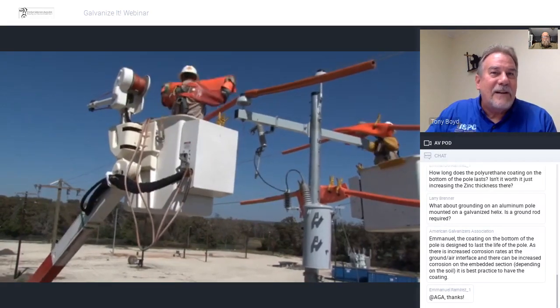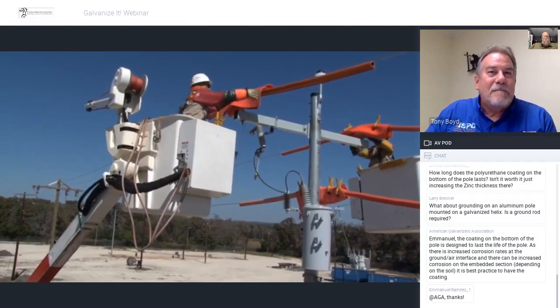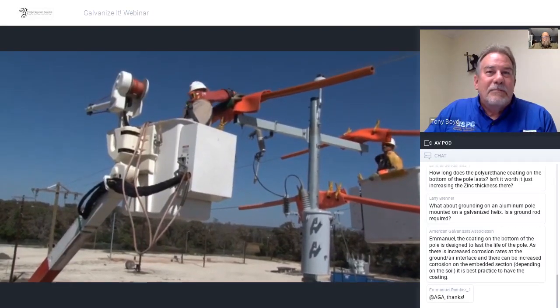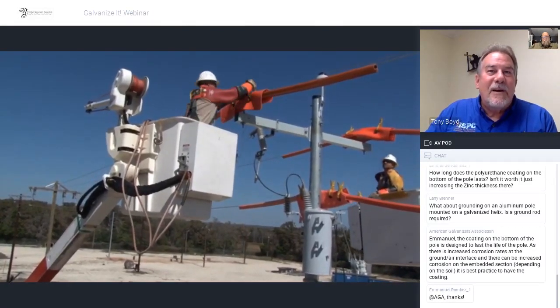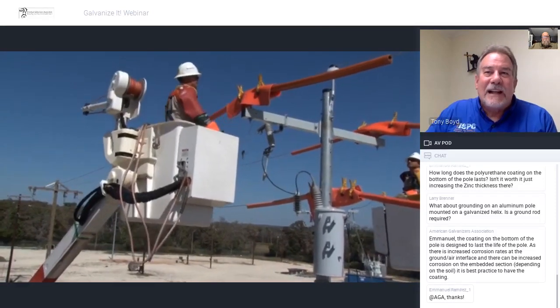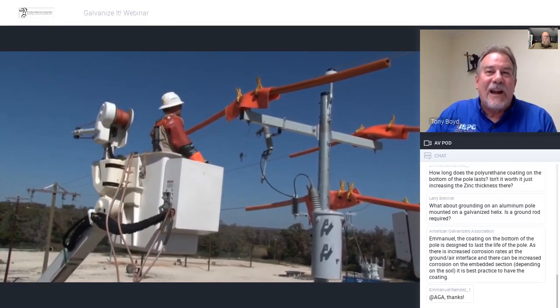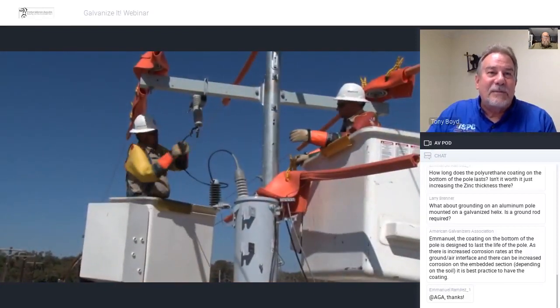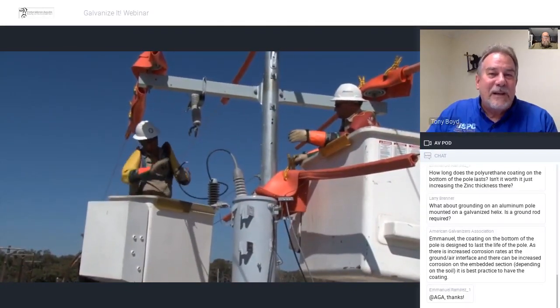They'll be working in this area to rig block and tackle for the transformer replacement. So they rubber up all the conductors that will be nearby. Some rubber goods on. He's in a line hose position on the wire, and blankets over the insulators improve their odds for safety while they're working in the high voltage area. The primary lead is disconnected from the cutout and from the transformer's primary bushing.